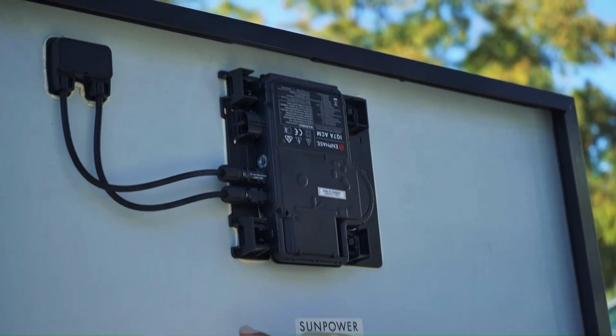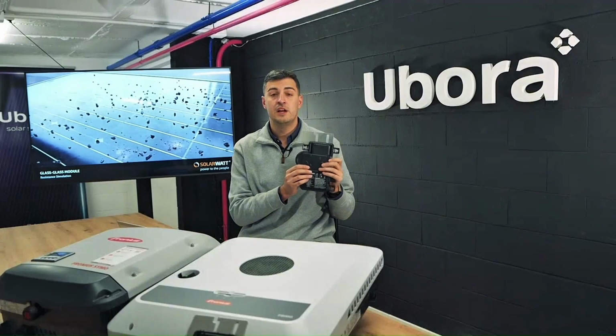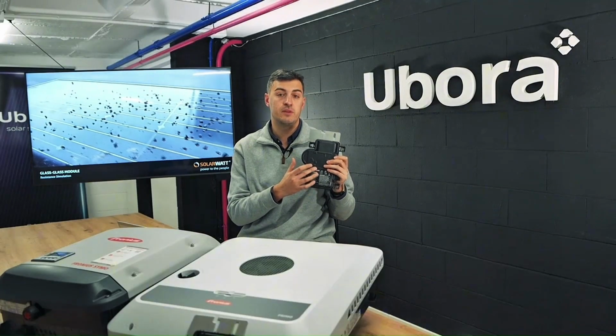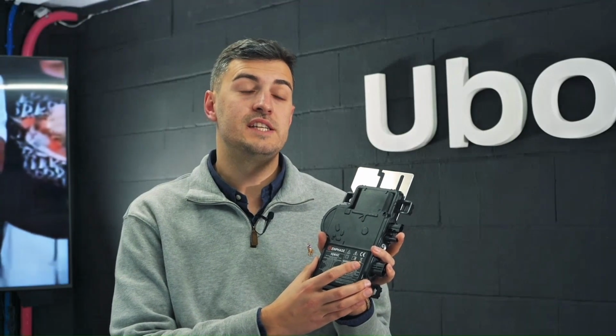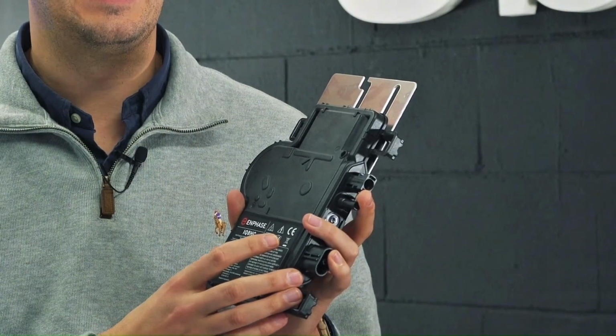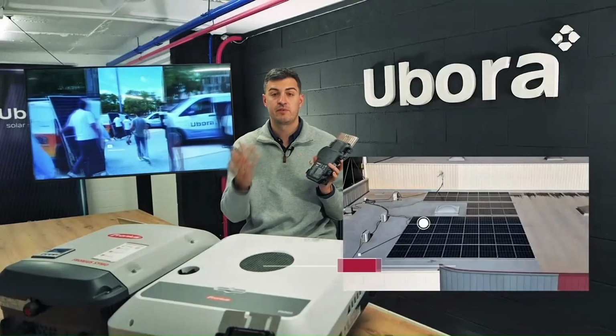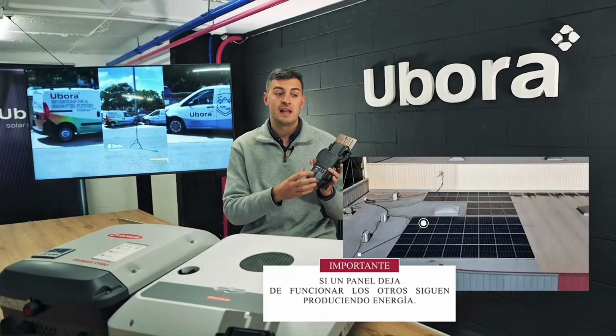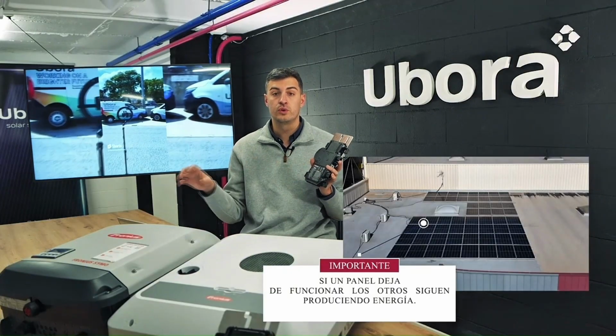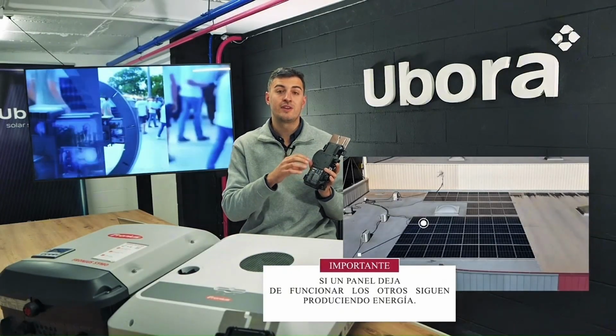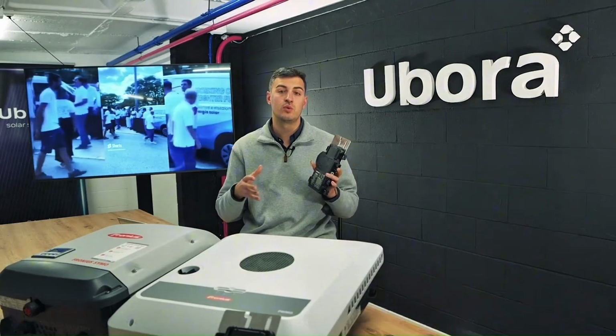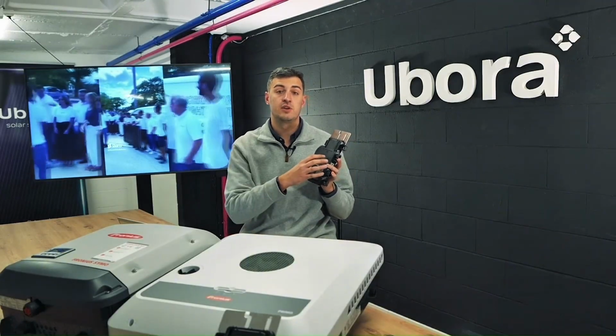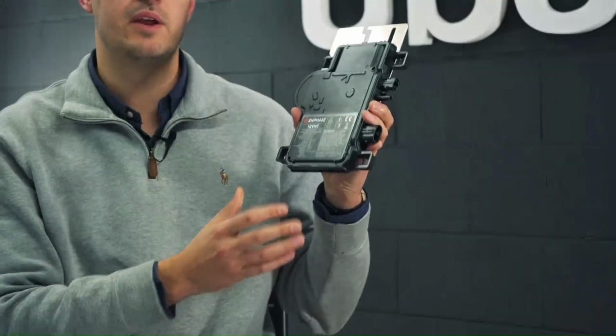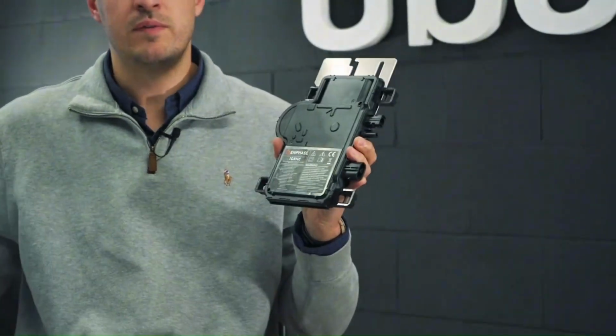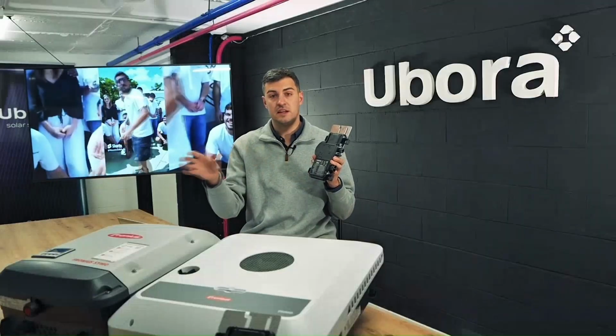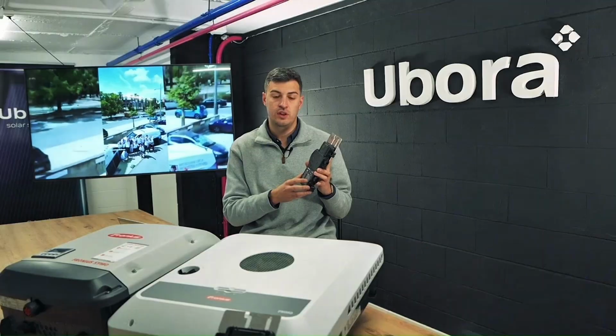The microinverter is directly connected to every single panel. This is exactly what makes the panel's electrical output individually customizable. So if a panel is affected in its production, whether by dirt on the panel, a poor connection, or damage to it, the energy from that panel doesn't affect the other panels. Why? Because we don't route all that DC energy through a string to a central inverter. Instead, the DC current from the panel is converted to AC by the microinverter, and we carry it separately to the home installation or supply.